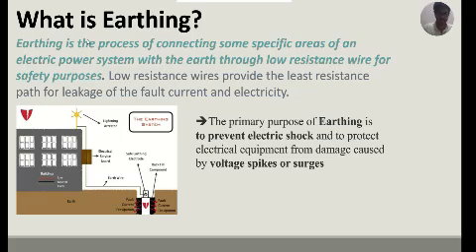As I mentioned here, the process consists of connecting some specific areas of an electrical power system through a low resistance wire for safety purposes. As this wire conducts the electricity, it is dissipated into the ground, and this process we call earthing. The main purpose of earthing is to provide a safe path for fault currents or excessive currents to dissipate into the earth, thereby preventing electrical shocks and protecting equipment from damage or voltage spikes or surges.